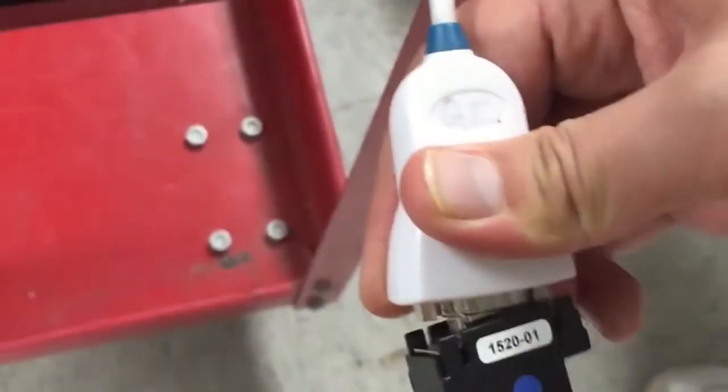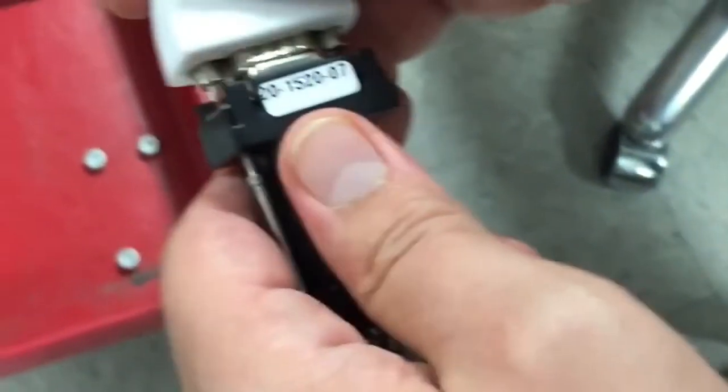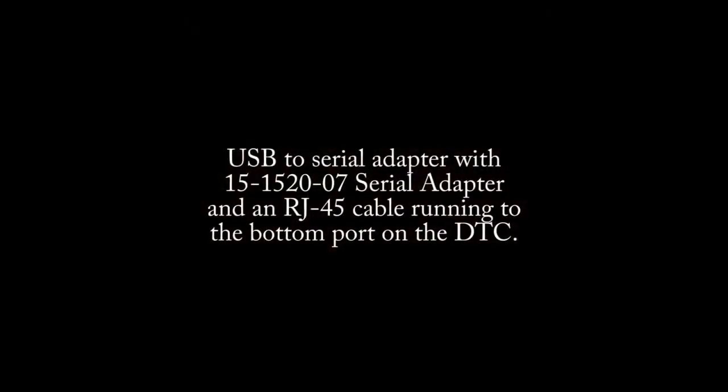To configure the DTC, you must use a USB serial adapter with a 15-1520-07 serial adapter cable, and an RJ45 cable running from your computer to the RJ45 port on the bottom left of the DTC.